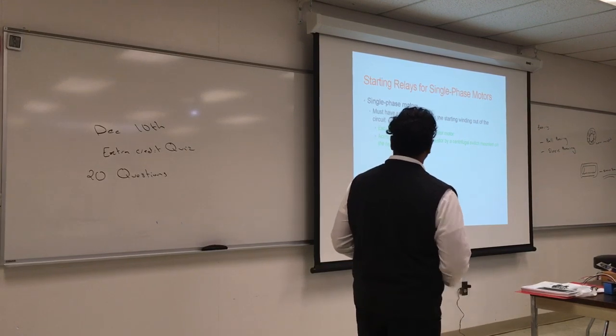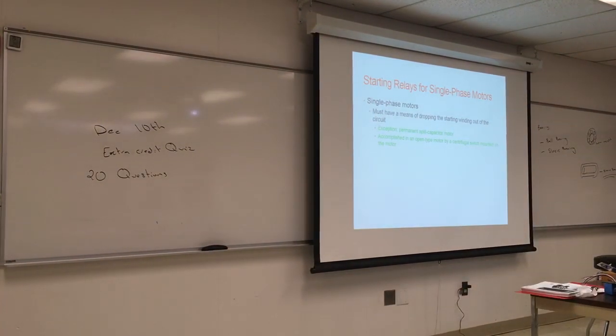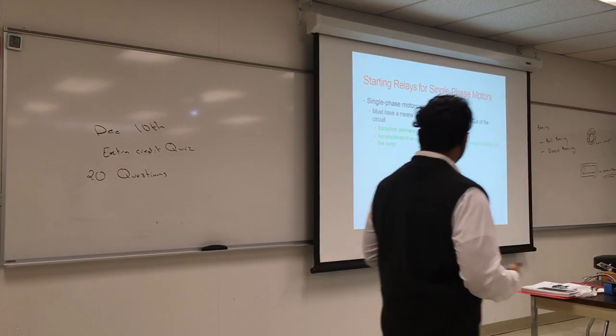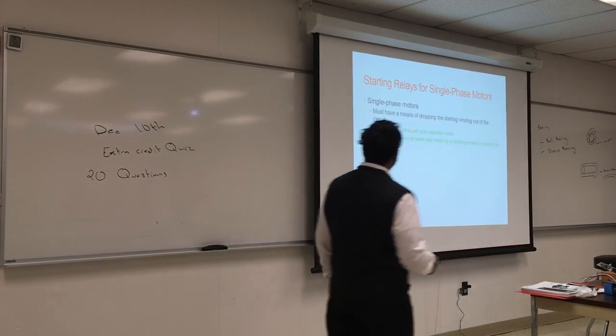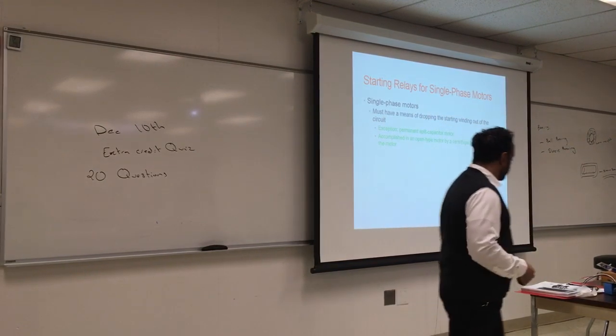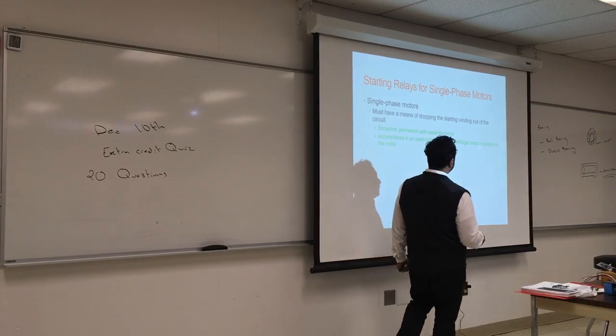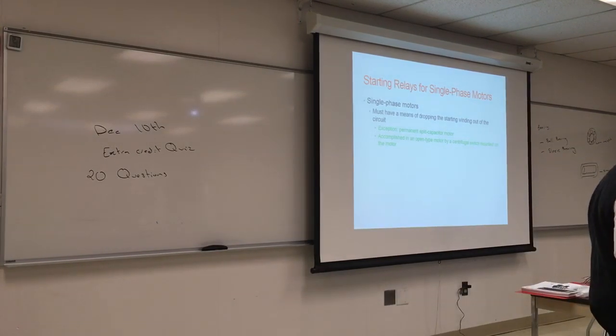Starting relays for single phase motors. So the starting relays, what they do is just drop off your start winding. When we did the motor lab, we heard a click. When the motor clicked, it means you dropped the start winding. If you did not drop the start winding, what will happen? It will burn. It will just keep going faster and faster and it will heat up and eventually it will burn the motor.